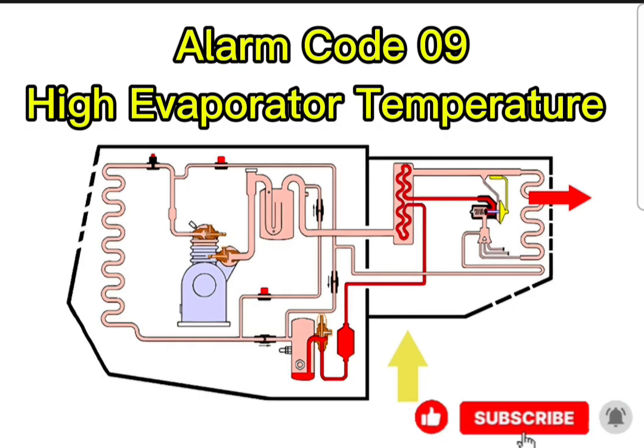Well, when you run a commercial refrigeration cycle, you are constantly pulling moisture out of the air. That humidity inevitably condenses and freezes on the icy evaporator coils. Naturally. If you just leave it running continuously, you will eventually build up a massive, solid block of ice that chokes off all airflow. So it suffocates. Yeah, the unit will stop cooling entirely, suffocated by its own freezing temperatures. So the system has to periodically fight its own ice buildup? It has to actively introduce heat.